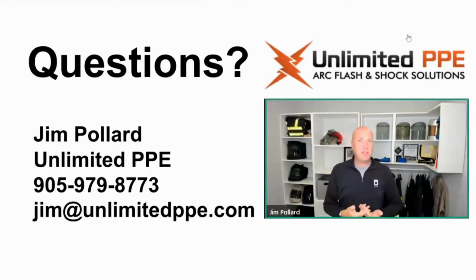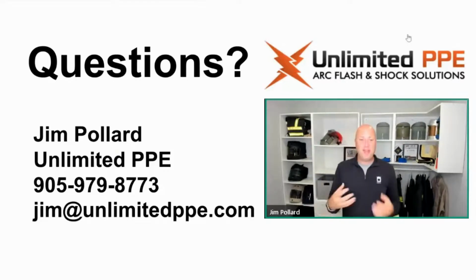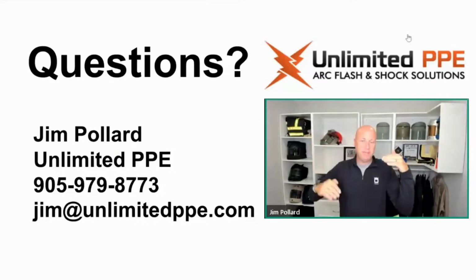Whenever I say there's Arc Flash PPE above 40 calories, I always get these questions. So I've been answering these questions for a very long time. The actual blast or this pressure wave is more of a component of the short circuit fault current, which is part of the calculation that we use to calculate incident energy. But there is no direct correlation between the amount of incident energy and what that blast pressure might be.